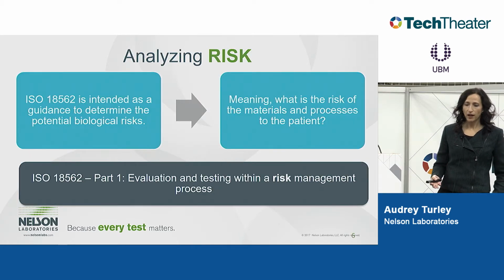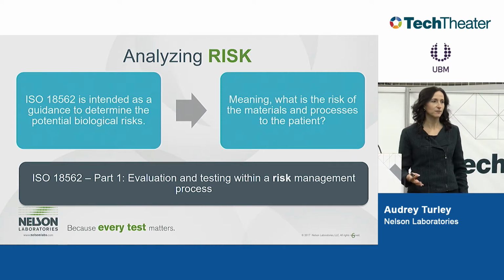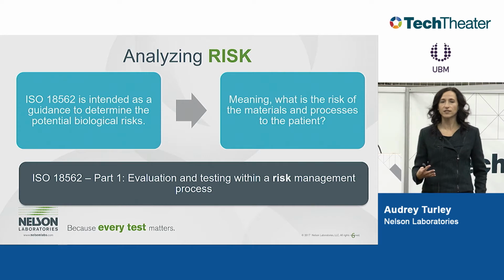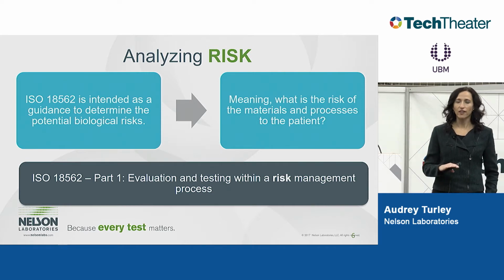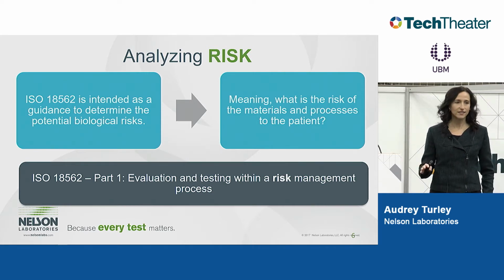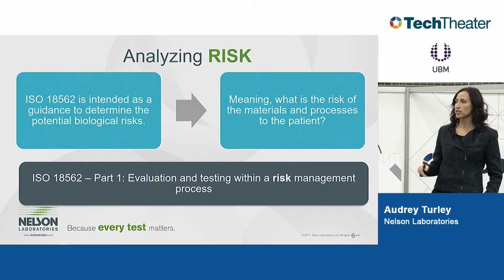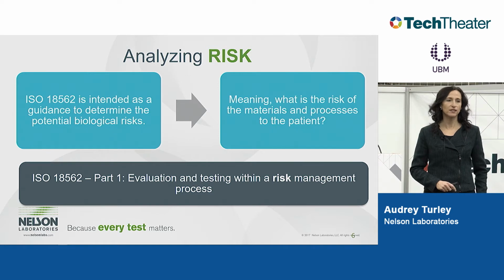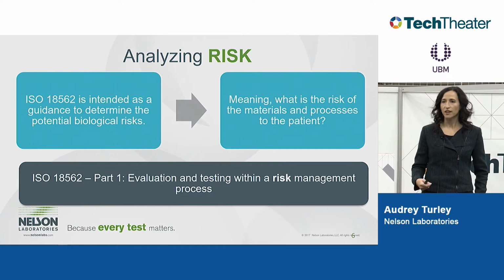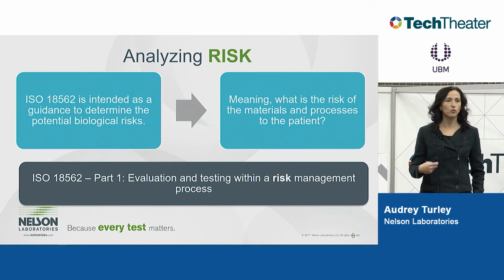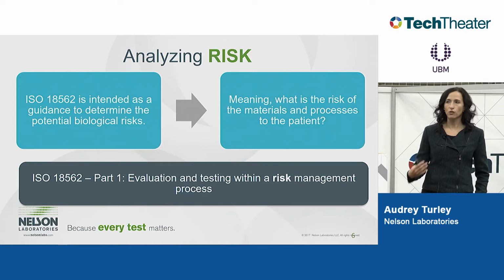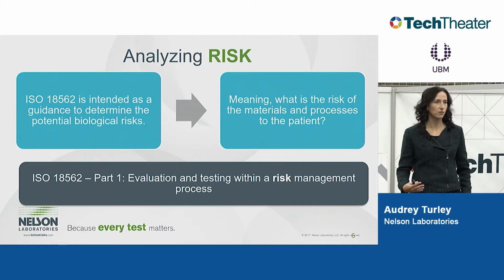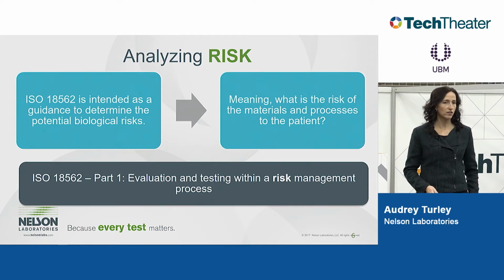So when we talk about our initial risk assessments, it's good to realize that that is where the conversation should begin. 18562 has a parallel title that is the same as ISO 10993-1. So it's evaluation and testing within a risk management process. We can't drive this home enough that the agencies want you to start with what you already know and your specific risks of your device. So what you know about your device, what you know about your patient population, we're going to lay all of our cards out on the table.